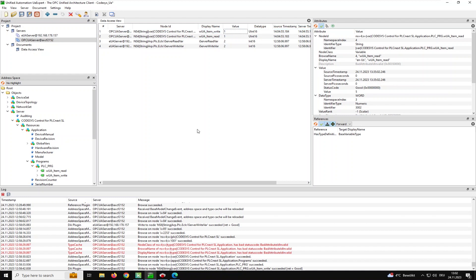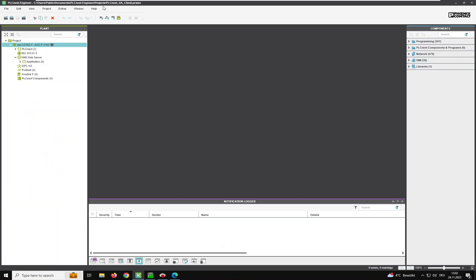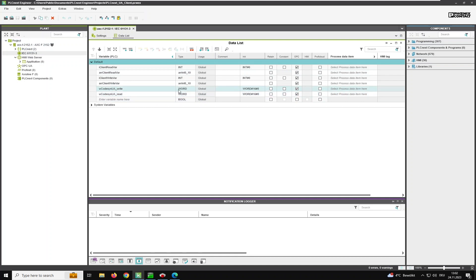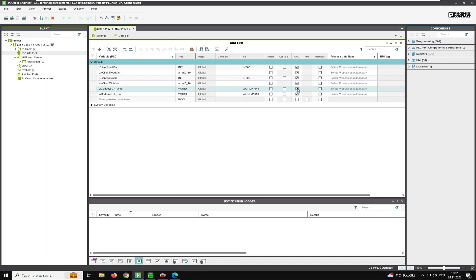We can now proceed with the client configuration in PLCnext Engineer. I've opened the OPC UA client application and added two additional variables — a write and read variable with the same data type as the Codesys ones. Since PLCnext Engineer 2023.9, it's no longer necessary to mark those variables as OPC — you can do it, but it's not required. If you have an earlier version, you have to activate this checkbox.